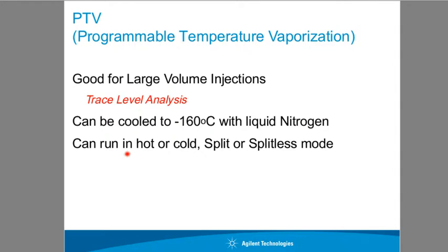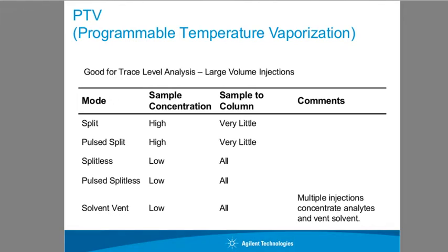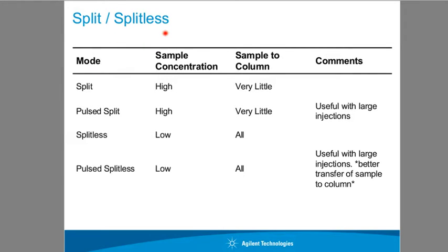And you can run it in hot or cold and split or splitless. So, again, a little bit more flexibility than some of the previous inlets as well. Here it's going to give you a little bit of a table on where you can use it and what the benefits are. And on to the splitless. We're going to spend a lot more time talking about the splitless and the parameters used with this just because it's the most commonly used inlet.